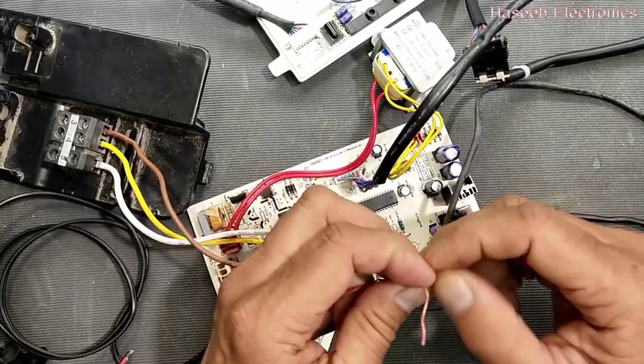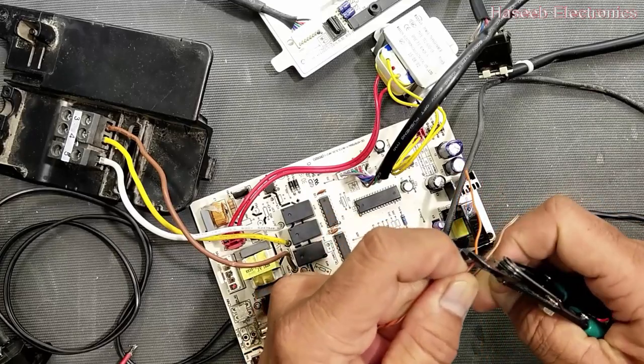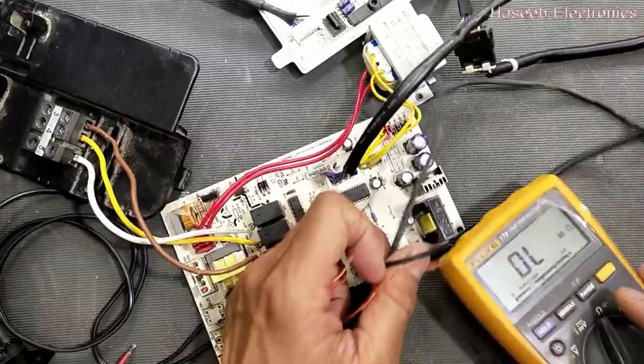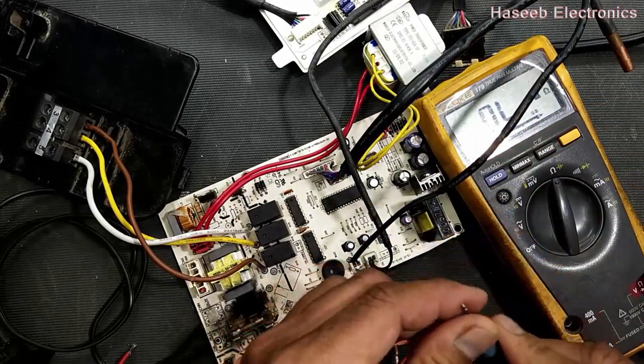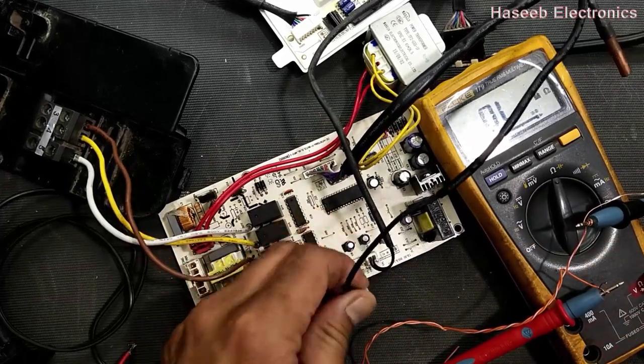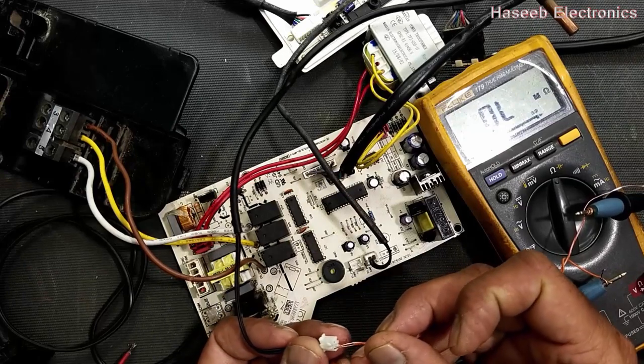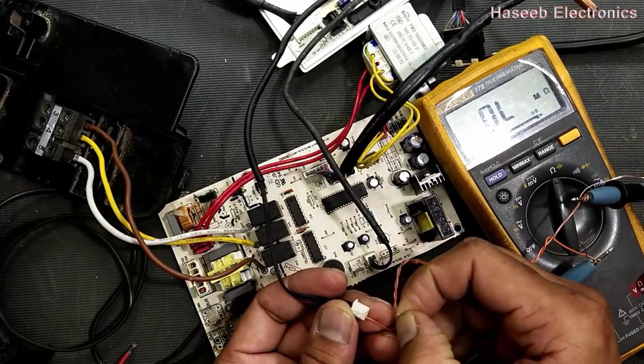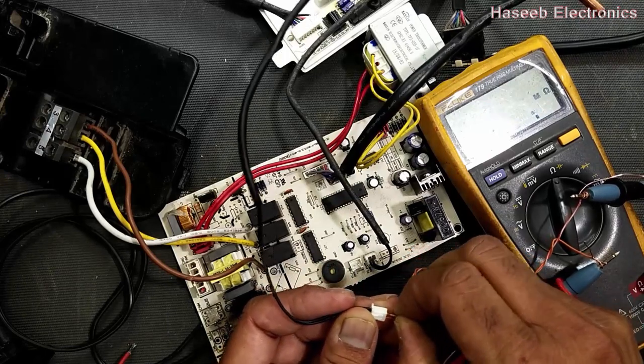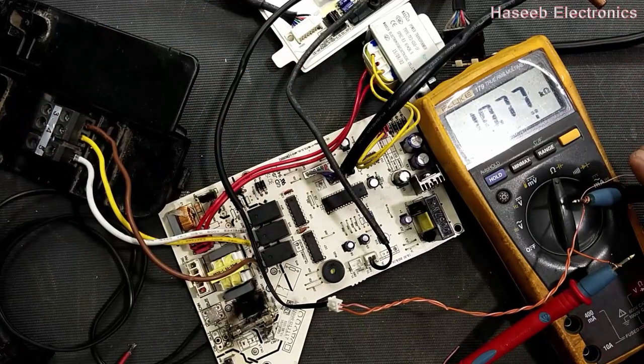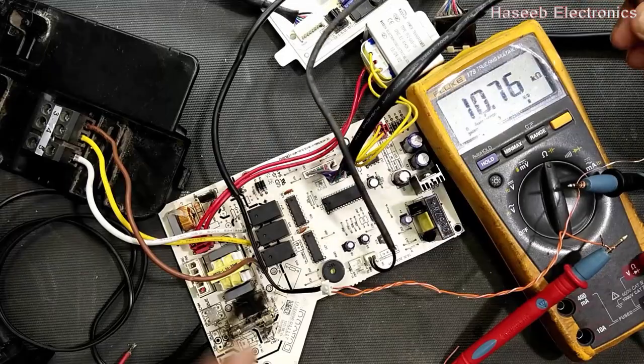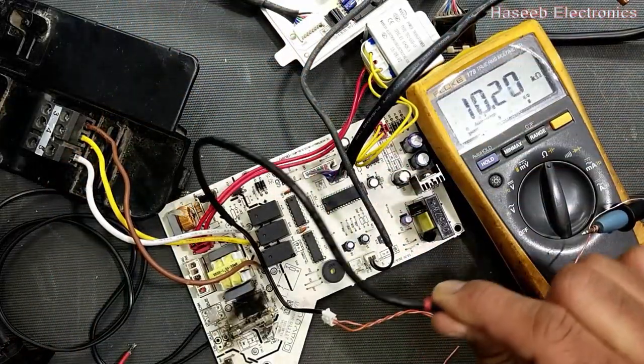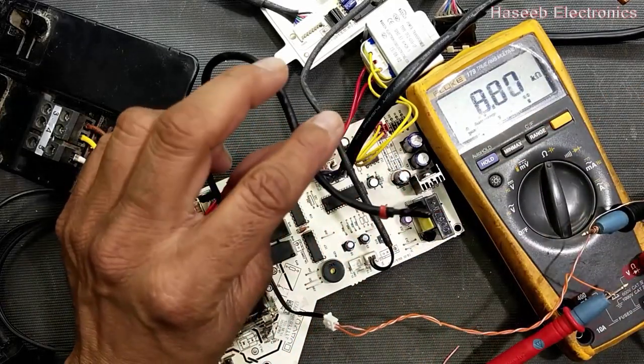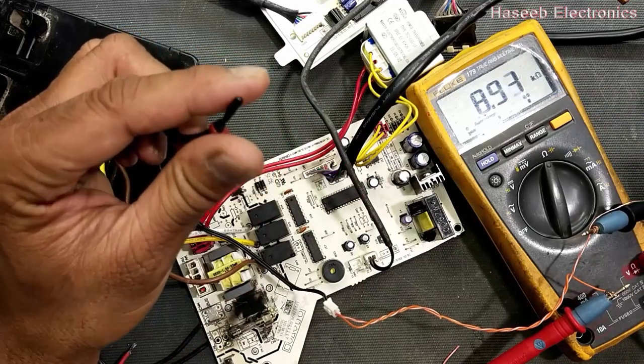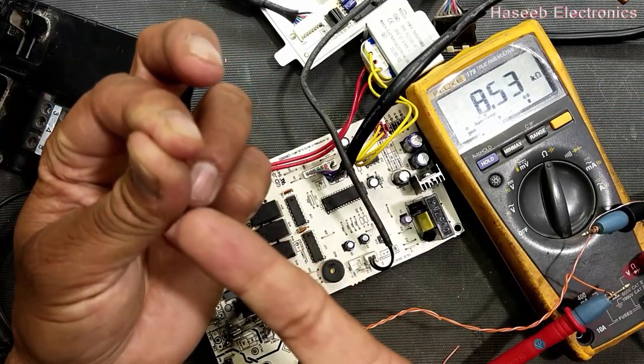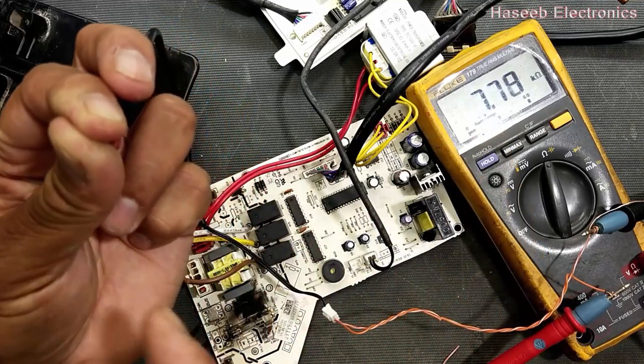We can test these thermal sensors very easily using a multimeter in the ohm range. Set multimeter to ohm. Remove the sensor from the cable connector. We can verify if the sensor is working or not. It is giving 10 kilo ohm. Now hold the sensor. The resistance should change. If we leave the sensor, the resistance will increase. It is increasing. When I hold it in my fingers, its temperature increases and the resistance decreases. So the sensor is working properly.